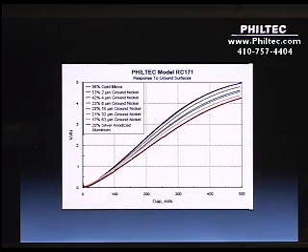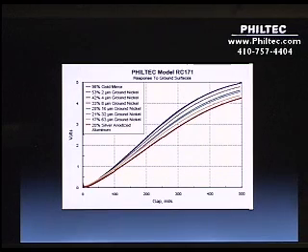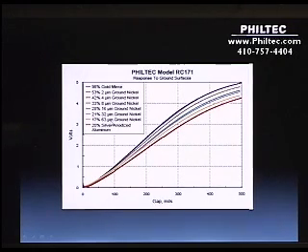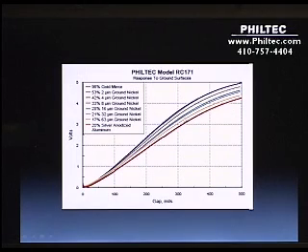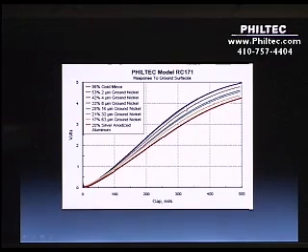To extend this one further step, when we scan the sensor over ground nickel specimens that have a variation of surface roughness from 2 micro-inch up to 63 micro-inch roughness, you can see the spread of the data with the roughest ground nickel surfaces. The sensor response approaches the response on the typical diffuse anodized target, and with the smoothest ground surfaces the sensor's response approaches the response of a specular surface or that of a front surface mirror.